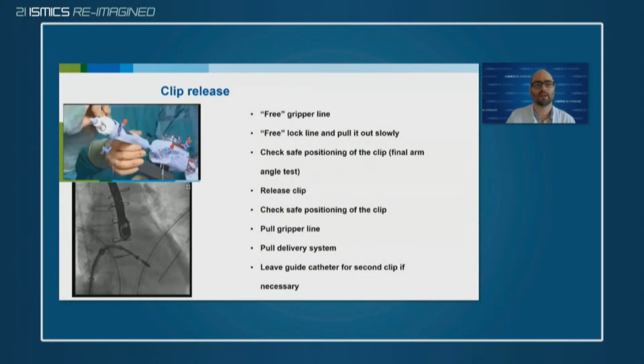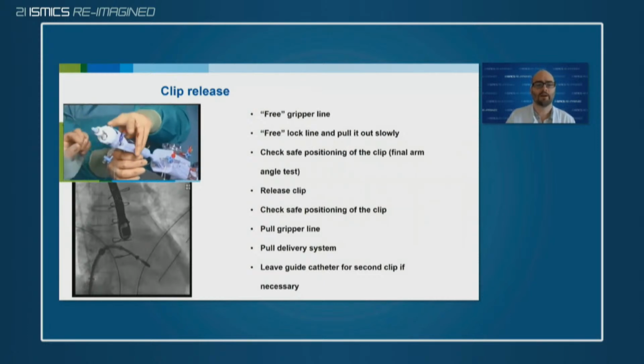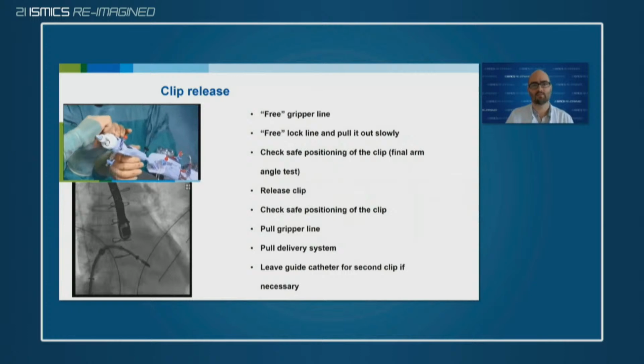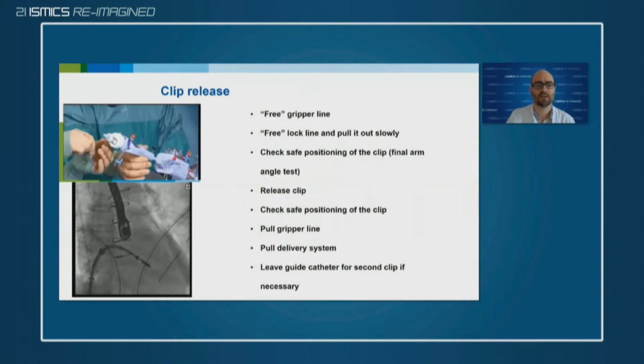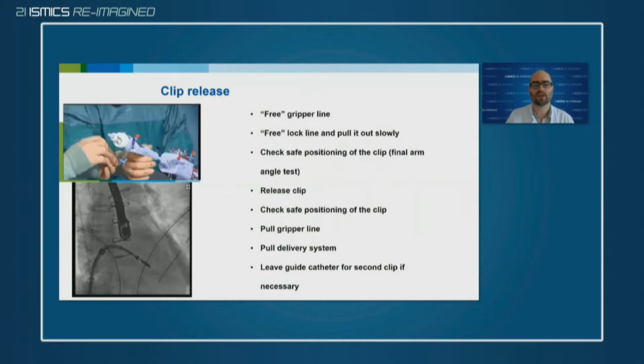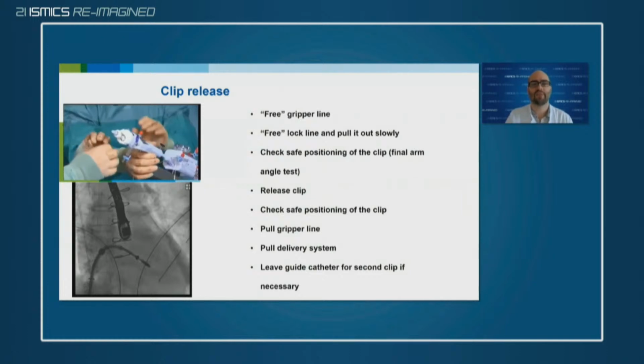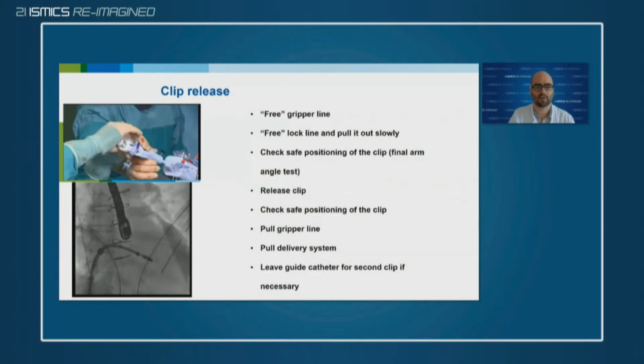Both lines, the gripper line and the lock line, are released. Only the lock line is pulled back. Then you check the safe position of the clip. You do the final arm angle test at this point of time. Then you release the clip. You check the safe position again, and then you pull the gripper line, which is till now the last safety net to hold the clip.